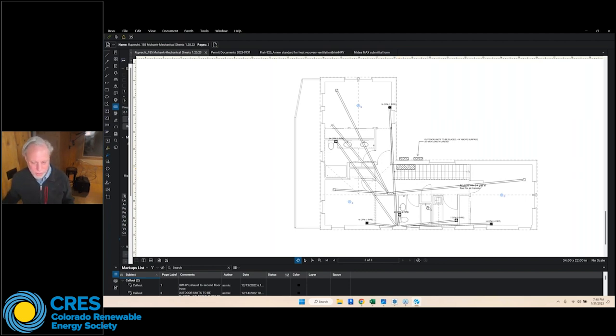Why go through all this? Because we're saving at least $10,000 on the cost of equipment installation, and we're saving significantly on the efficiency of the system. These Mideas are substantially more energy efficient than low velocity flow units that go into the ceilings, or VRF units where you have multiple heads with one compressor. All of those units drop dramatically in efficiency compared to single mini split units. So it's kind of the best of both worlds in that sense.